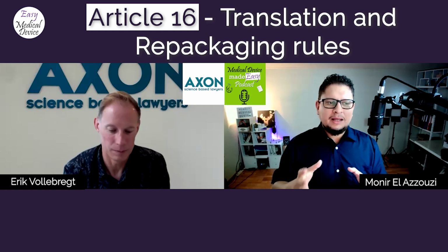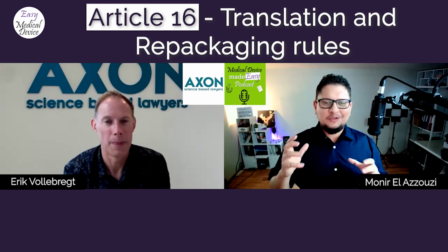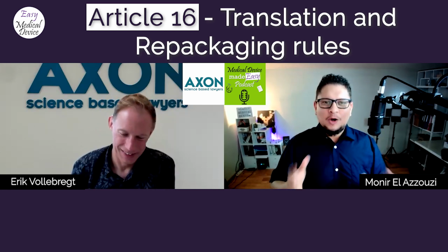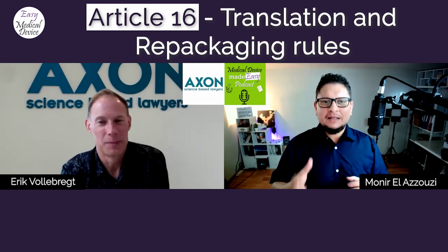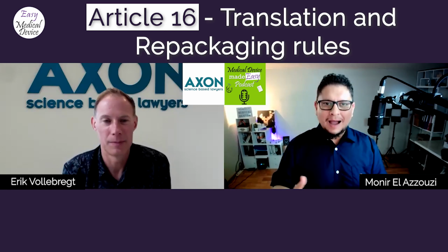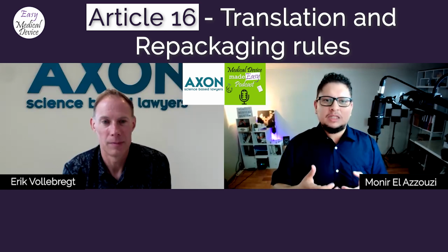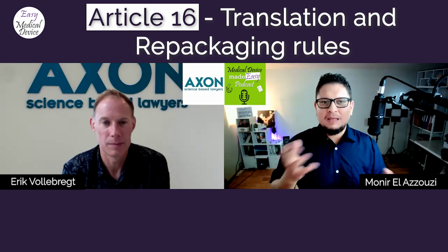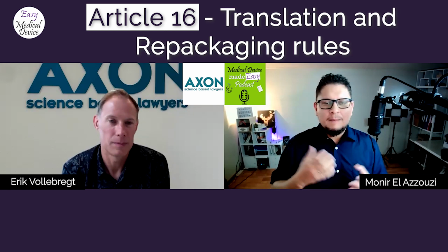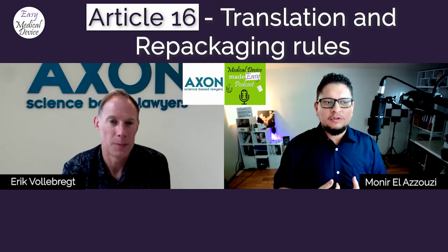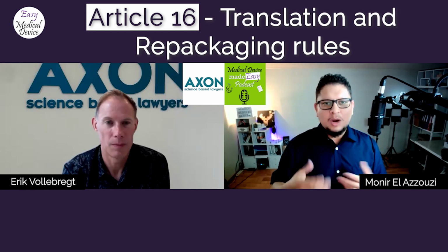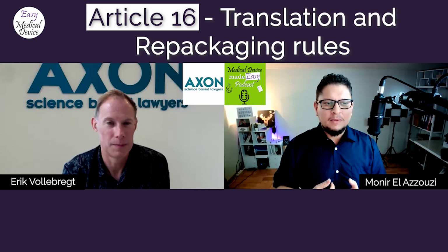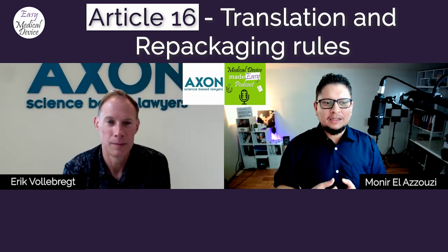So I hope that, I mean, I tried to play the devil's advocate and put some of the questions that the manufacturers are asking. So I hope that now people really understand why this is in place and what they have to do, and the fact that it should be applicable by now. And we discussed here about the legacy devices, where maybe there are still some discussions, but there is no transition period for this Article 16. So it's something that you have to consider as soon as possible, because otherwise you can be non-compliant, so placing devices on the market in a non-compliant way.